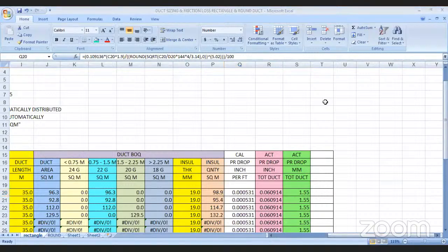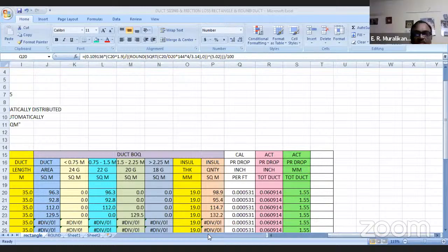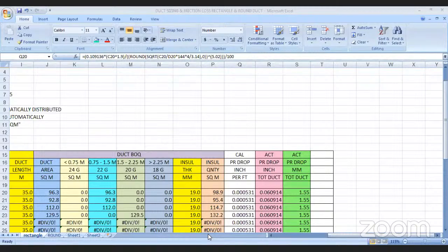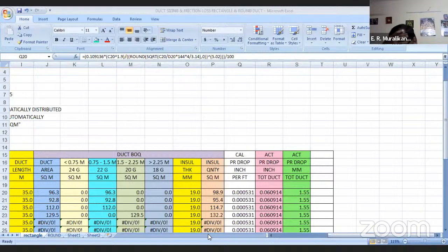If you have a wall mounted grill within 1 meter from an FCU, such as in hotel guest rooms, can we apply only acoustic insulation, given that acoustics will affect the FCU static? See, I already told you this is only for AHUs with ducting, not FCUs and small units, and I told you in the starting. For ducted indoor units and the small FCU, it's not needed because the static is low, about 1 to 2 static. The throw is very short in FCUs and the like. The only thing is that the person in the hotel has to feel the temperature. He is not bothered whether he is getting air or not. As the room is cool, he'll be happy. So in those cases we cannot discuss. I'm only talking of air handling units with ducting.